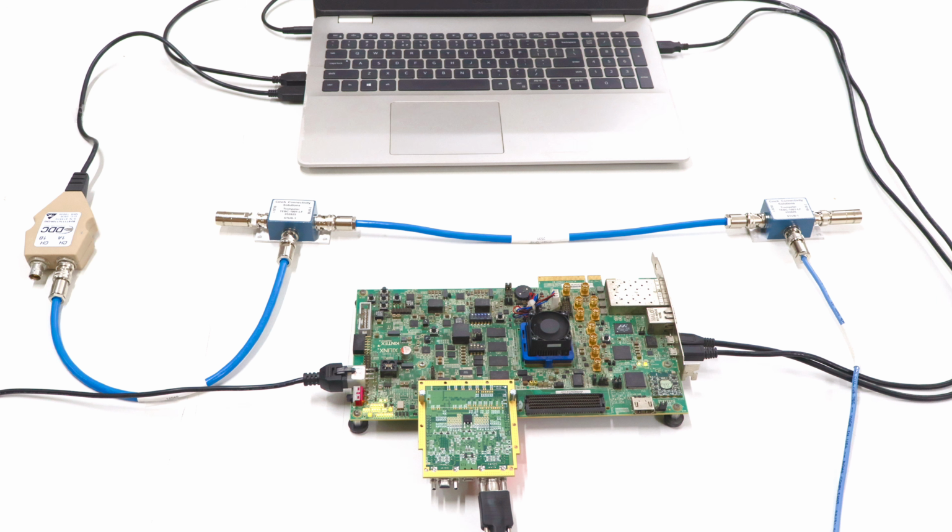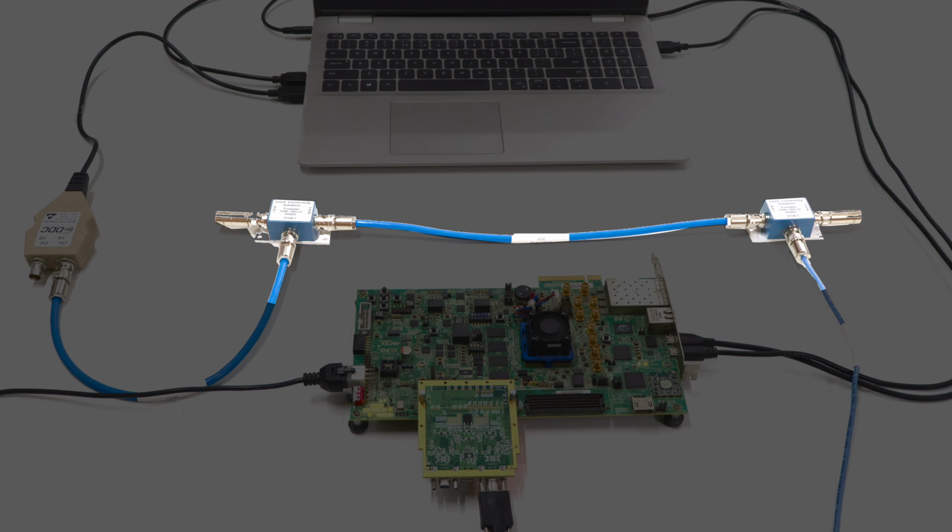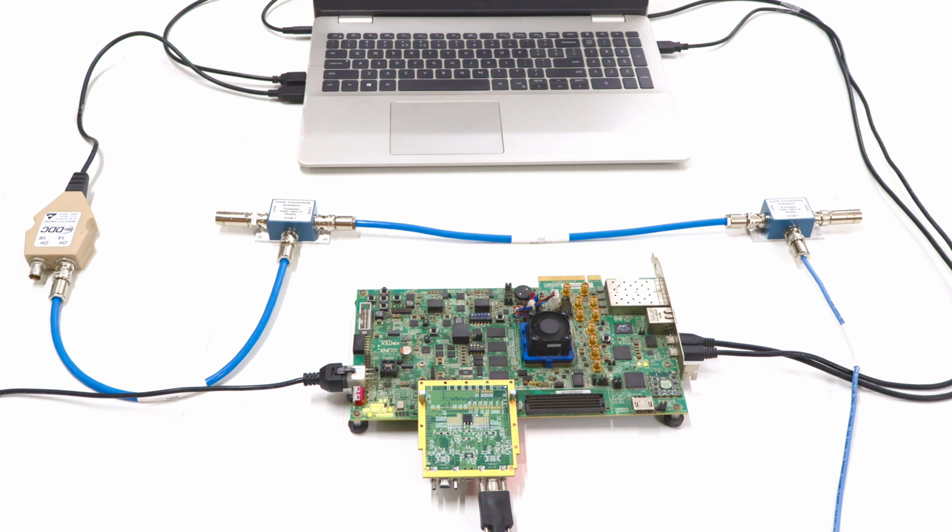The FPGA and DDC's USB to MIL-STD-1553 adapter are connected by a MIL-1553 cable, shielded twisted pair with two stubs, having 78 ohm characteristic impedance termination at both ends, exactly as the standard requires. iWave's MIL-STD-1553 IP Core supports bus controller, remote terminal and monitor terminal modes, which can be selected from the configuration menu, where the monitor terminal acts as a passive listener on the bus. Now let's walk through each mode live on the hardware.